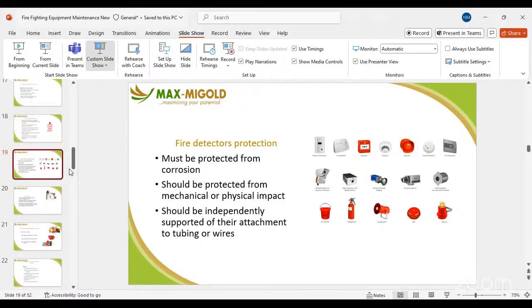Then smoke detectors should be independent, and supported by a system that is a bit resistant to the fire zone. What do I mean? You cannot connect your fire alarm to the factory or to the premises alarm. We have the premises power system, so what do we have? We have a battery powered alarm system wired to the panel. So inside the fire panel of the smoke detector panel, we have batteries. So even though we power the panels by the premises electricity, when there is a power outage, the batteries take over.